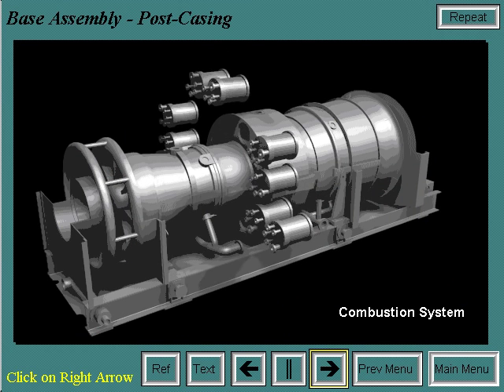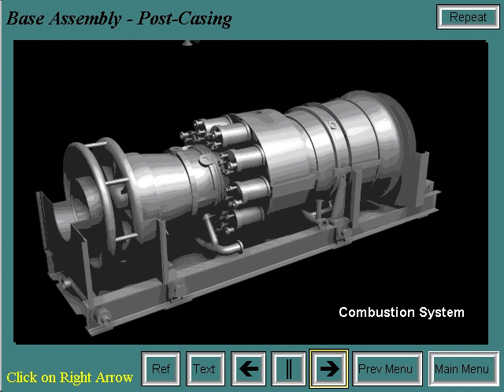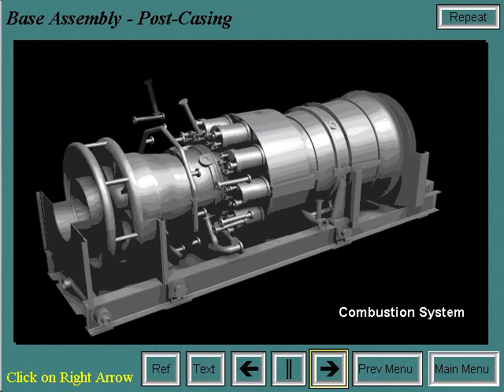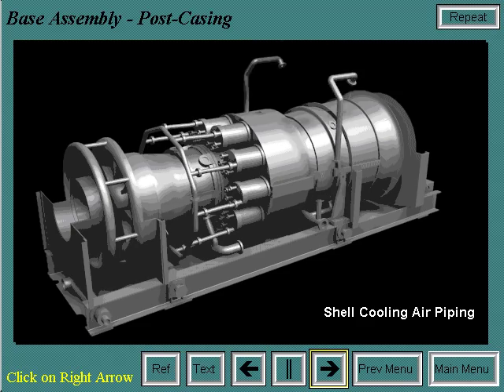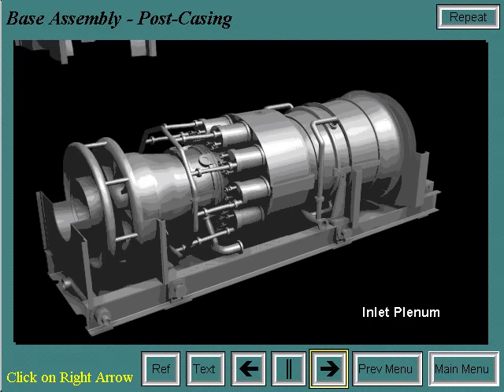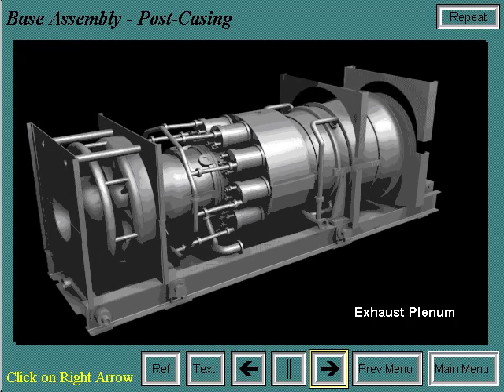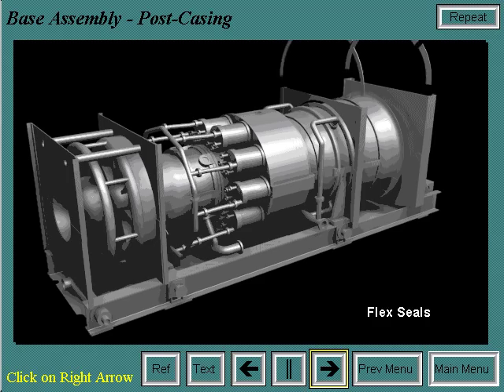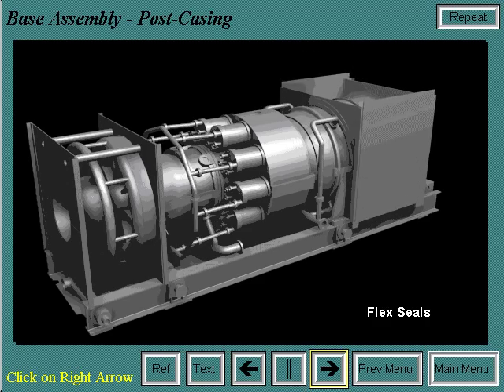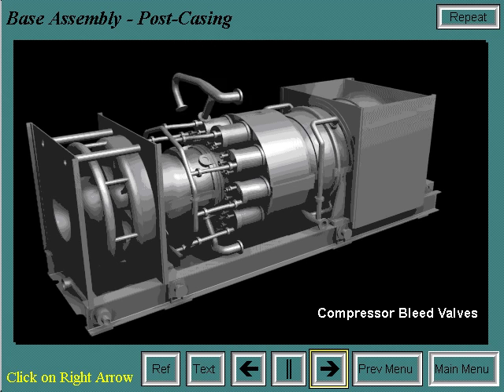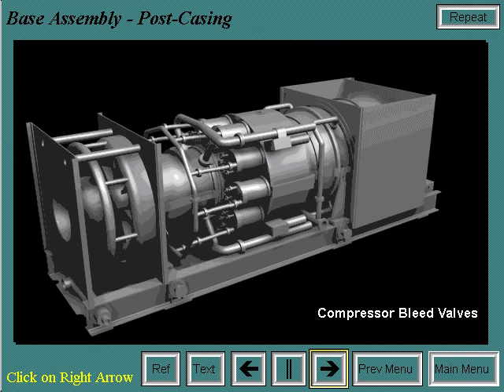Once the casings are on, the combustion system is installed. Next, the shell cooling air piping is installed. Air comes from off-base blowers to facilitate shell cooling in the turbine and exhaust casings. Then the inlet plenum is installed, followed by the exhaust plenum. The flex seals keep the exhaust gases from escaping into the turbine compartment or out to atmosphere while allowing for thermal expansion. Finally, the compressor bleed valves are installed, which are operational during startup and shutdown to protect the unit from surge.